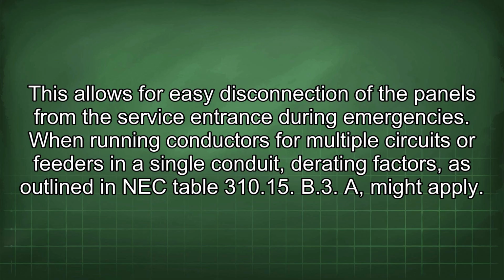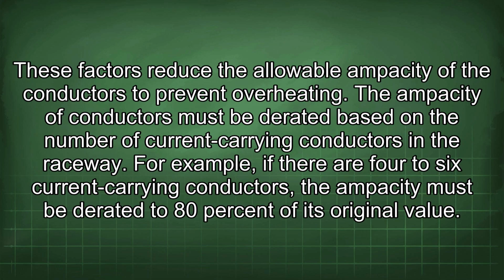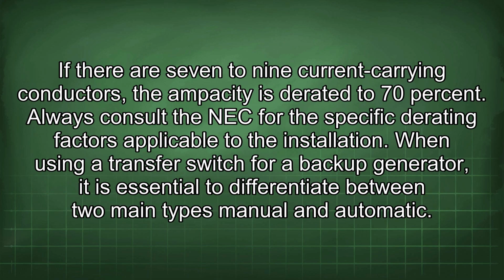When running conductors for multiple circuits or feeders in a single conduit, derating factors, as outlined in NEC Table 310.15(B)(3)(a), might apply. These factors reduce the allowable ampacity of the conductors to prevent overheating. The ampacity of conductors must be derated based on the number of current-carrying conductors in the raceway. For example, if there are 4 to 6 current-carrying conductors, the ampacity must be derated to 80% of its original value. If there are 7 to 9 current-carrying conductors, the ampacity is derated to 70%. Always consult the NEC for the specific derating factors applicable to the installation.